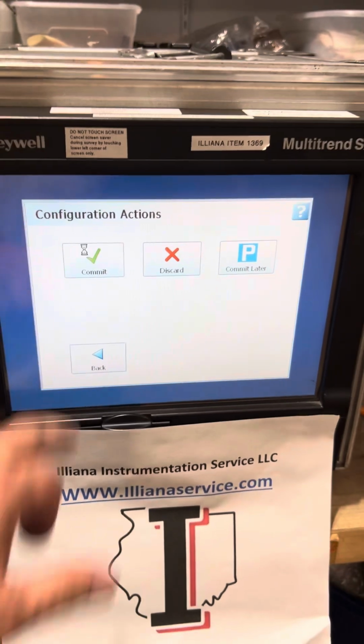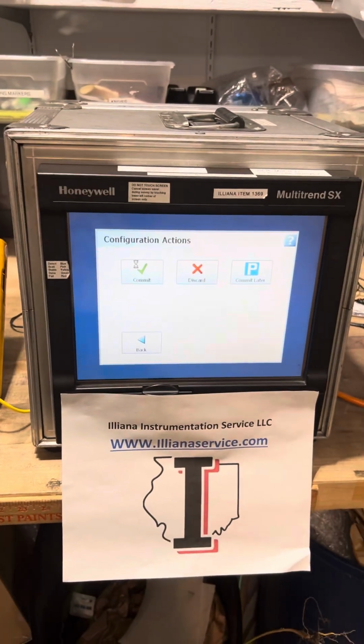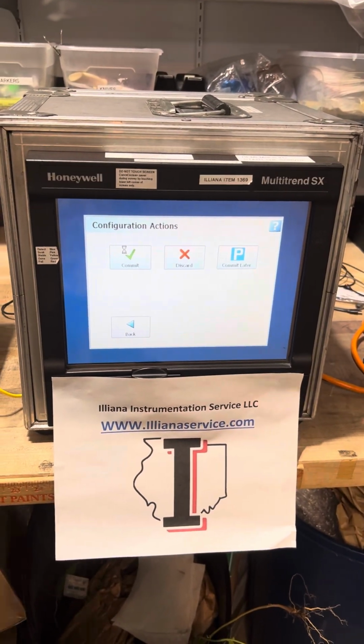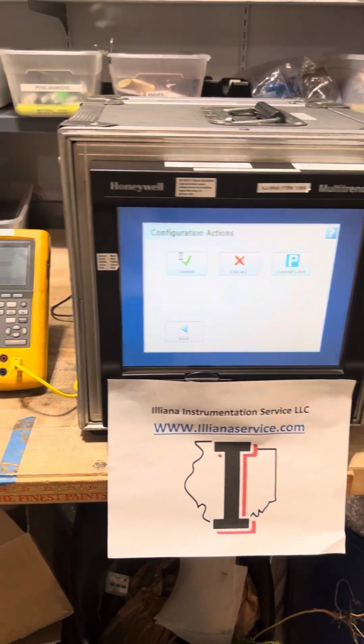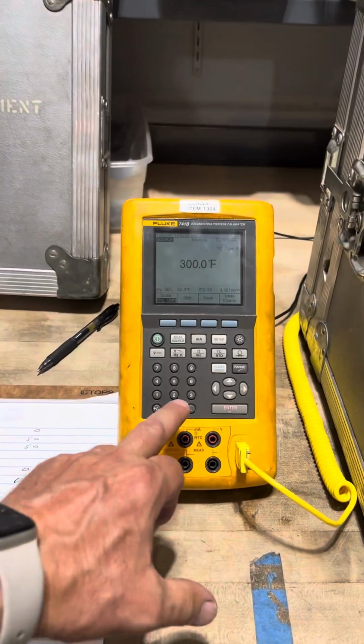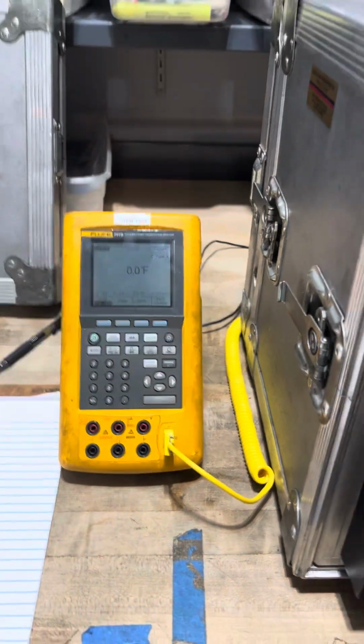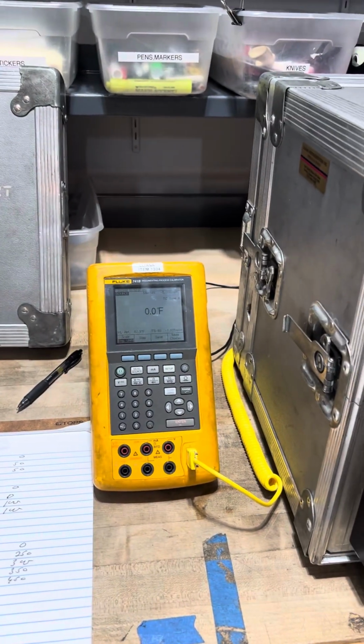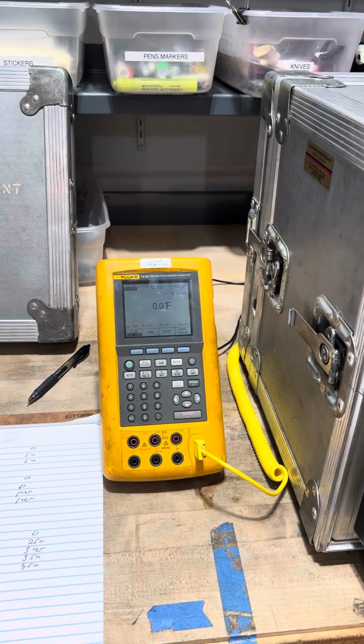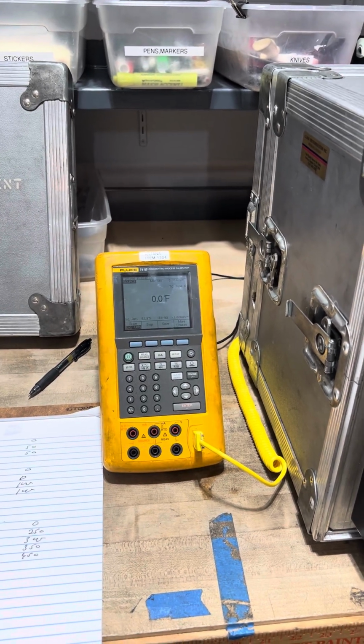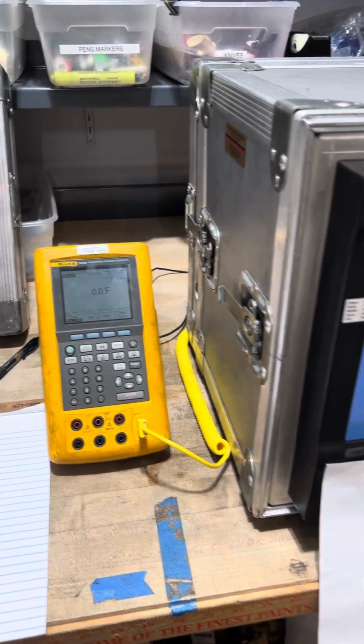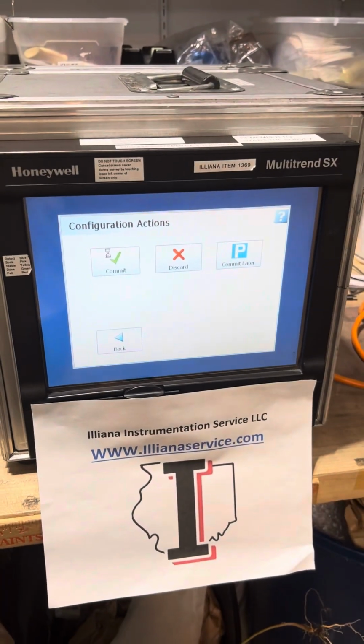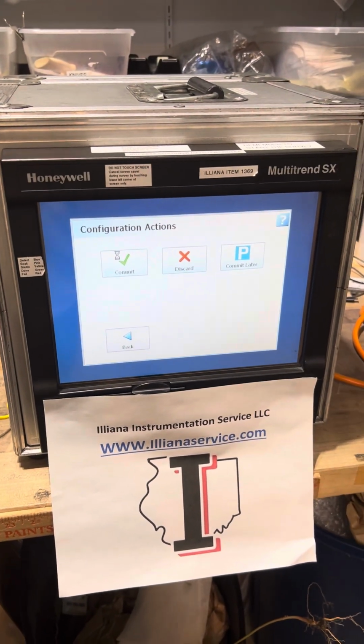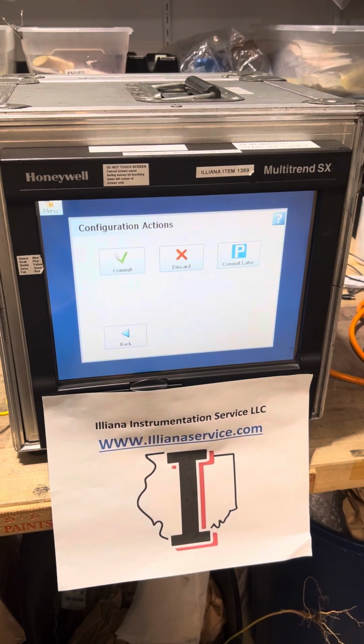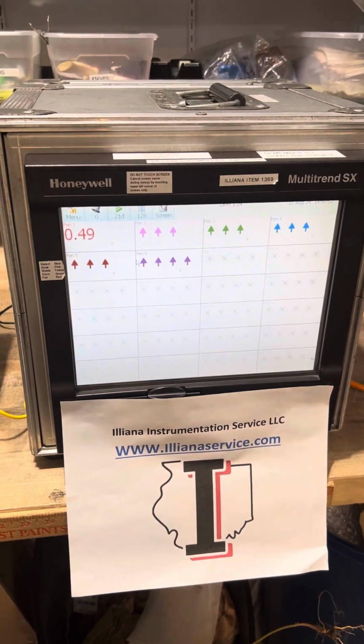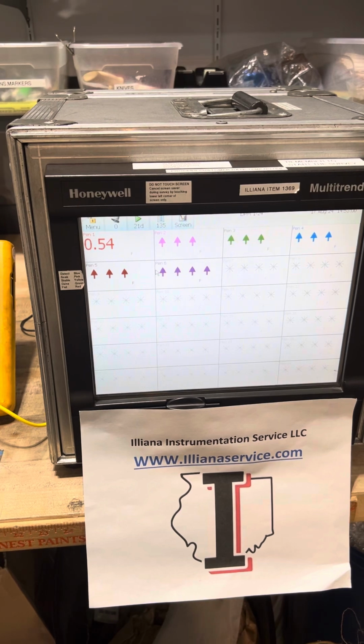So if I finish that and commit, it's going to take a second for the recorder to go ahead and write that information. And then I'm going over here to my Fluke calibrator and I'm going to set it to 0. And if you'll recall, at 0, I put in a correction of 0. So the recorder should read very close to 0 at this point in time. I'm kind of out in our warehouse right now, not super temperature controlled. And I'm not really doing a calibration of the recorder. I'm doing a demonstration of some of these features. But as you can see, it's pretty close to 0.